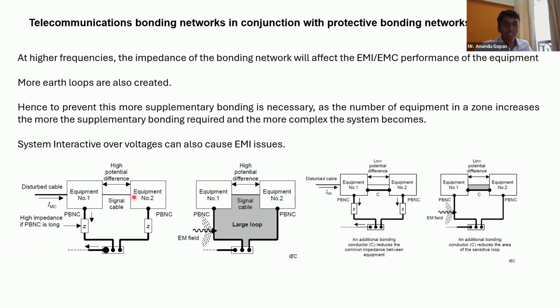So when you have such connections, if you have an electromagnetic field from some transient occurring outside, or maybe even 1 kilometer away from this system, how will it affect this? This will form a large signal loop. When you have such a large signal loop, the current induced in this loop will also be larger. You can face some failures inside these equipments. And in the next slide, I will be explaining about system interactive overvoltages. Basically, when you have an SPD and it works, what will happen to your cabling?